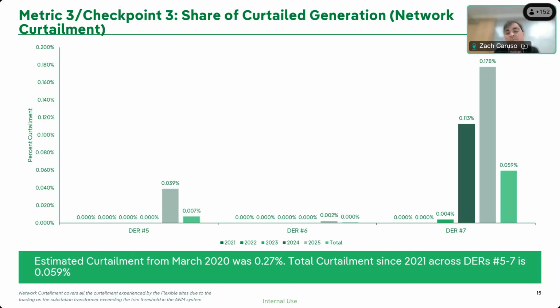So jumping to the point, this is the total amount of curtailment that we have seen from that thermal constraint for the Spencerport PVs. You can see in the early years, 21 through 22, we didn't see any curtailment at all. It did not curtail once. And you may know that 21 and 22 was COVID times, so there were some changes in the load profiles of the circuit. There were also some issues with the PV sites themselves. There was some downtime at certain times when we would expect curtailment to happen. That likely led to us never crossing that threshold until 2023, when we saw our first curtailment event, I should say.